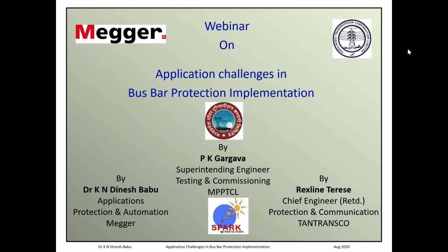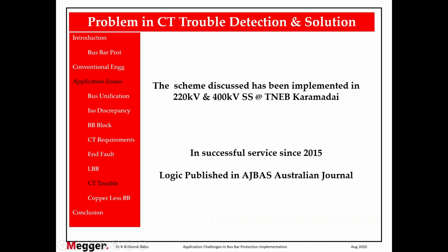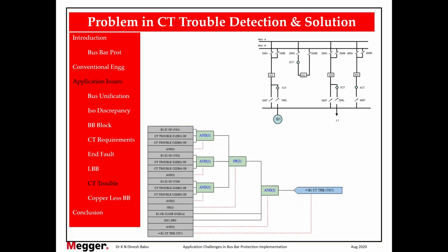Ma'am, generally we are not giving breaker status. So in this logic, we have to give breaker status to the relay. Yes, sir. Actually, in places where end fault is applicable, normally breaker status would be available. So in that kind of situation, we can use the breaker status to monitor the supervision current here. If breaker status is not available in the relay, then we have to modify the logic. We cannot use this logic shown here. This logic is based on the breaker feedback.